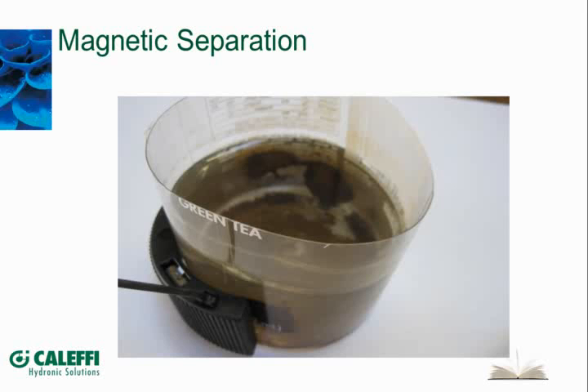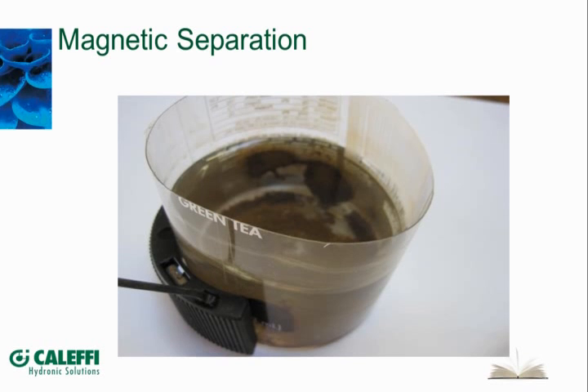As we start to work with variable speed circulating pumps that have permanent magnets in them, devices like this are going to become more essential. This is not something we want floating around with a wet rotor pump, especially with the magnets in it. An ECM pump has a strong permanent magnet type of motor. You can see this is just a powder. If you were to pour that out, it almost looks like you took a pocket knife to your pencil lead and shaved it. It's a really fine powder, and it's going to get into those pumps.